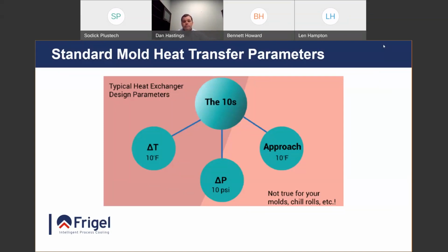10-degree approach. A lot of small TCUs have 1/4 inch solenoid valves. How much cooling approach can you get when you're sending water to the mold at maybe 20 gallons a minute, but the cooling on the outlet going back to the central system is 3/4, or I'm sorry, 1/4 inch? So if we can look at that, maybe going with a larger modulating valve that can properly adjust the opening, we can get a lower approach.